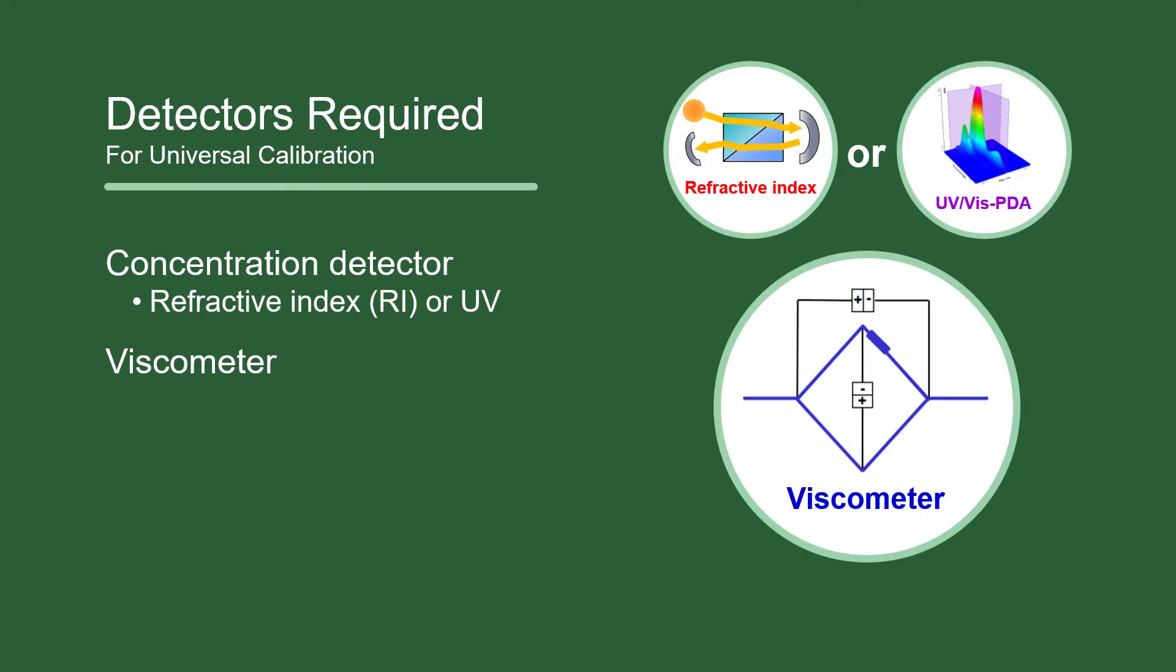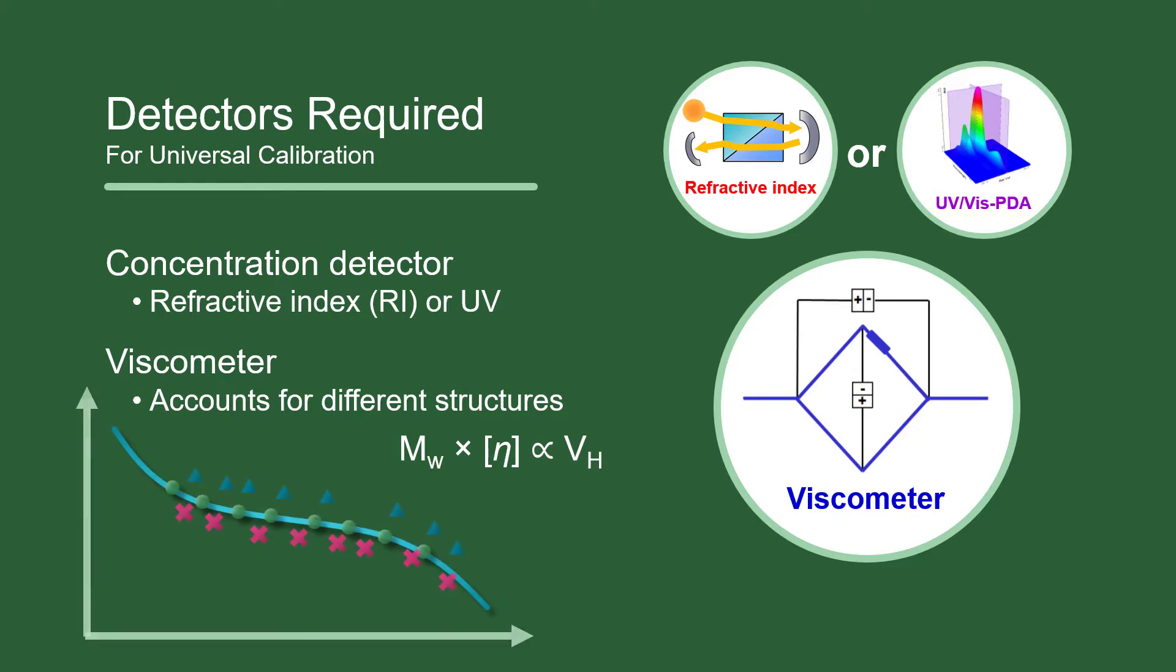A combination of a concentration detector and a viscometer detector is required for universal calibration. The presence of a viscometer detector accounts for differences in molecular structure and allows standards of different types to follow along a single universal calibration curve.